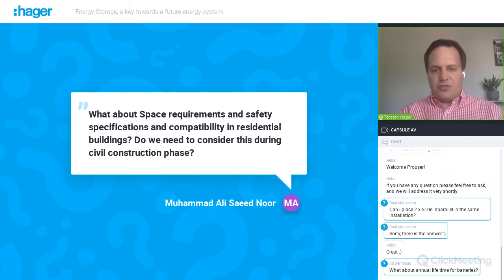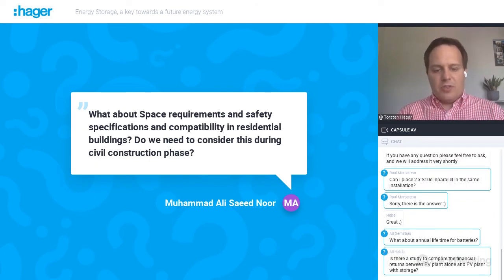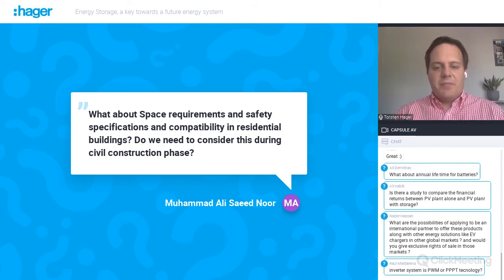That's the reason I say, generally, yes, you always have to take care about safety in this topic, and about the right location. It should not be too hot or too cold—not under 0 degrees, or better not under 5 degrees Celsius, because otherwise you could get problems in the chemistry. It should also not be too warm, for two reasons: first, you'd have to limit your power because the power electronics would reach their limit earlier, and second, the battery lifetime would decrease if it's too hot, as we saw before on that red diagram.